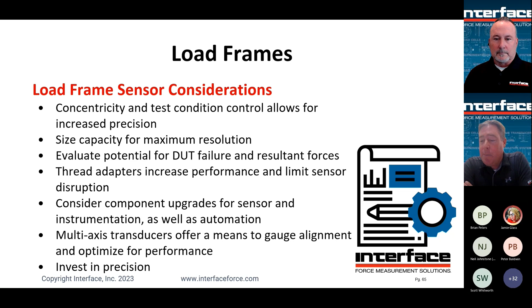Different examples of what we offer for frames. We've got a couple of new developments here. This is our model IF and VF, intended for essentially field verification of load cells and systems. Simple hand crank adapter rated up to 5,000 pounds. You could theoretically do some calibration on perhaps lower performance load cells, but it's primarily intended for use as verification, where you just want to load a load cell and an indicator display up to a given load and check its performance.